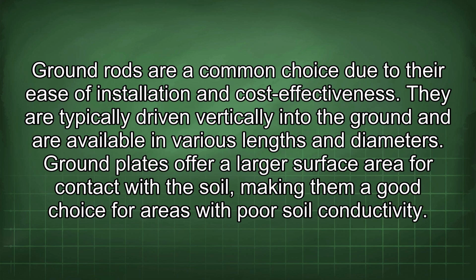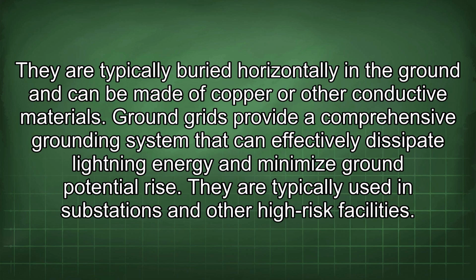They are typically driven vertically into the ground and are available in various lengths and diameters. Ground plates offer a larger surface area for contact with the soil, making them a good choice for areas with poor soil conductivity. They are typically buried horizontally in the ground and can be made of copper or other conductive materials.